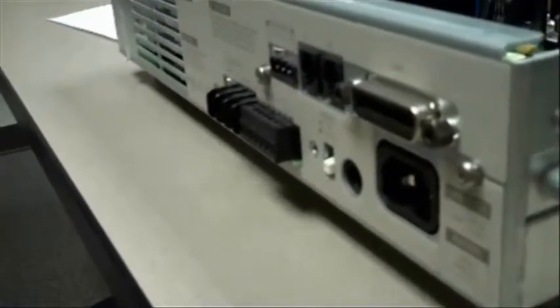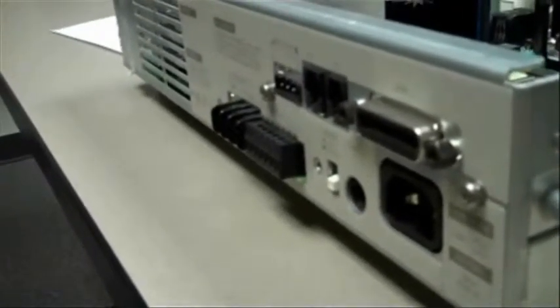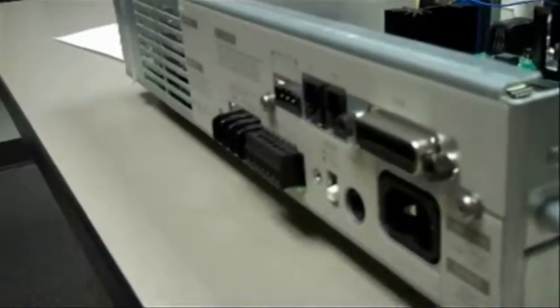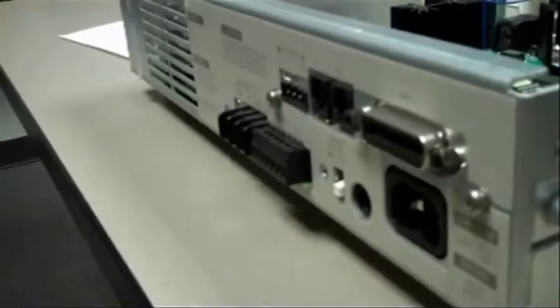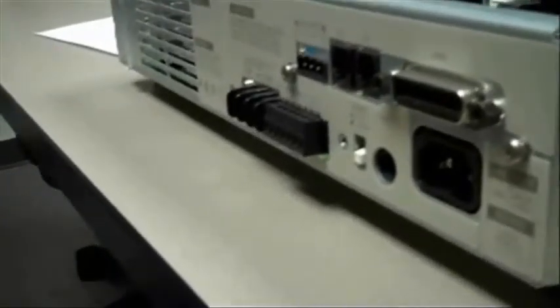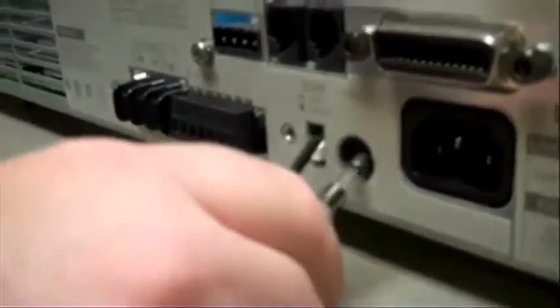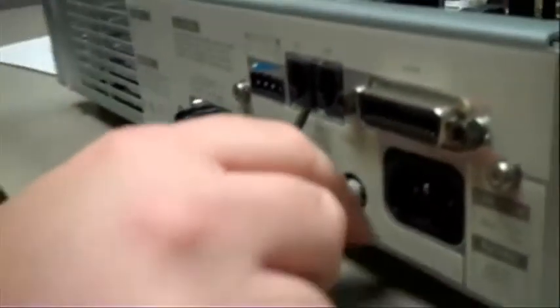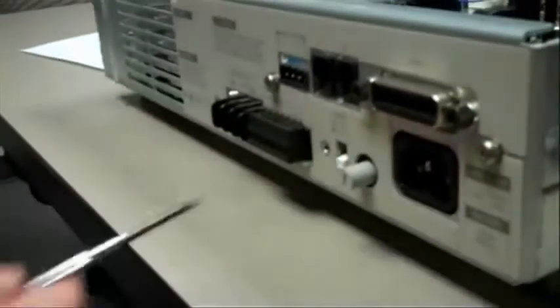For the fuses, in the manual in the section about changing the line voltage, it gives you a listing of all the different part numbers for the fuses and the ratings, so you can make sure you have the right fuse. If you don't have the right fuse, you might blow it and the power supply won't work until you put the right fuse in it.